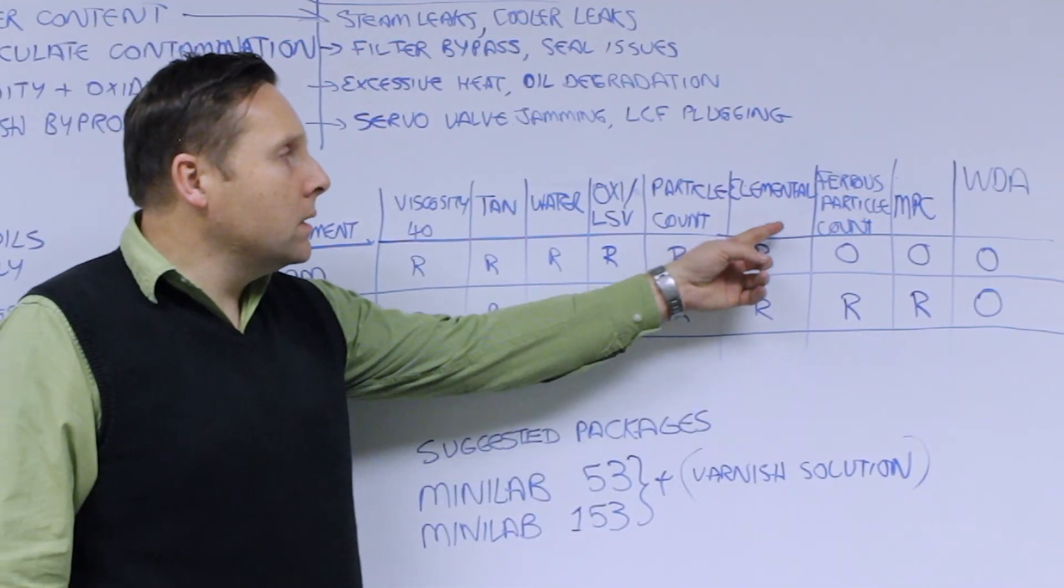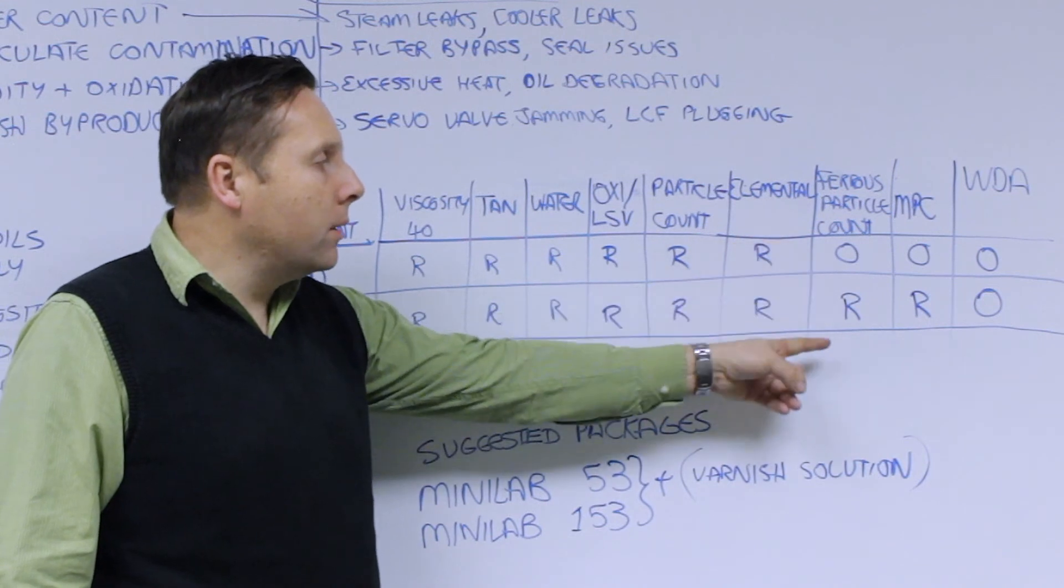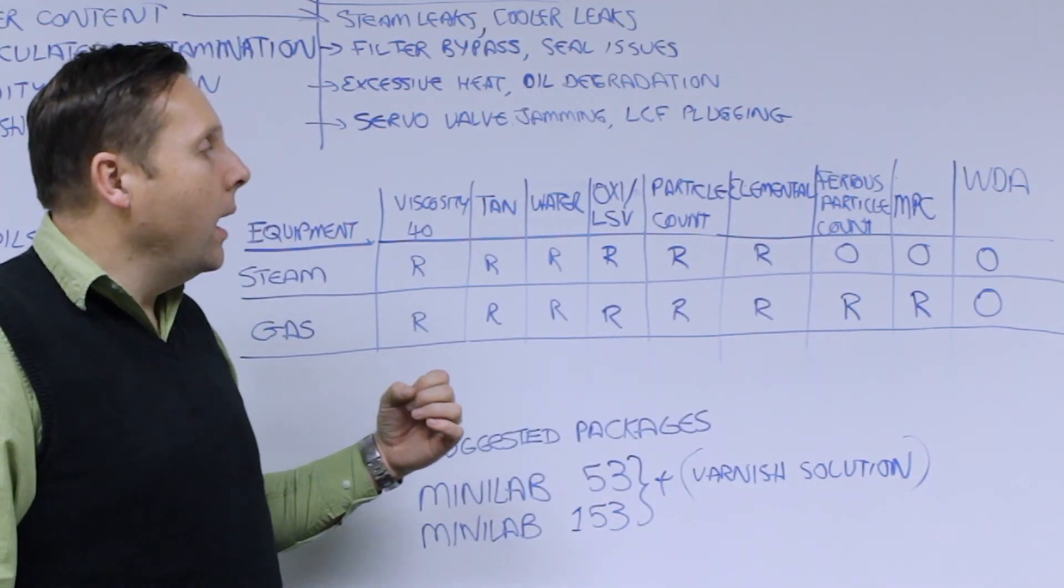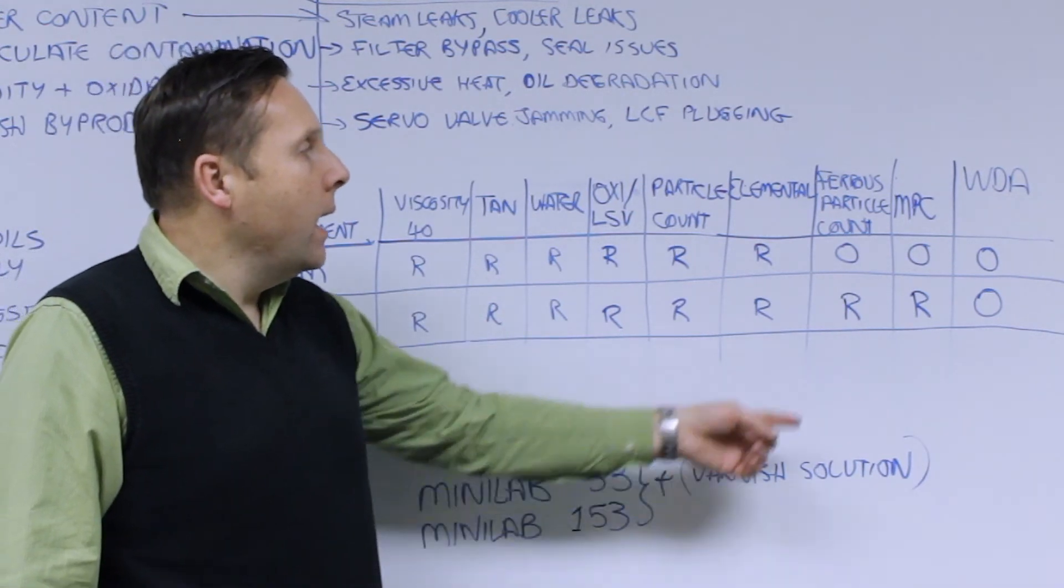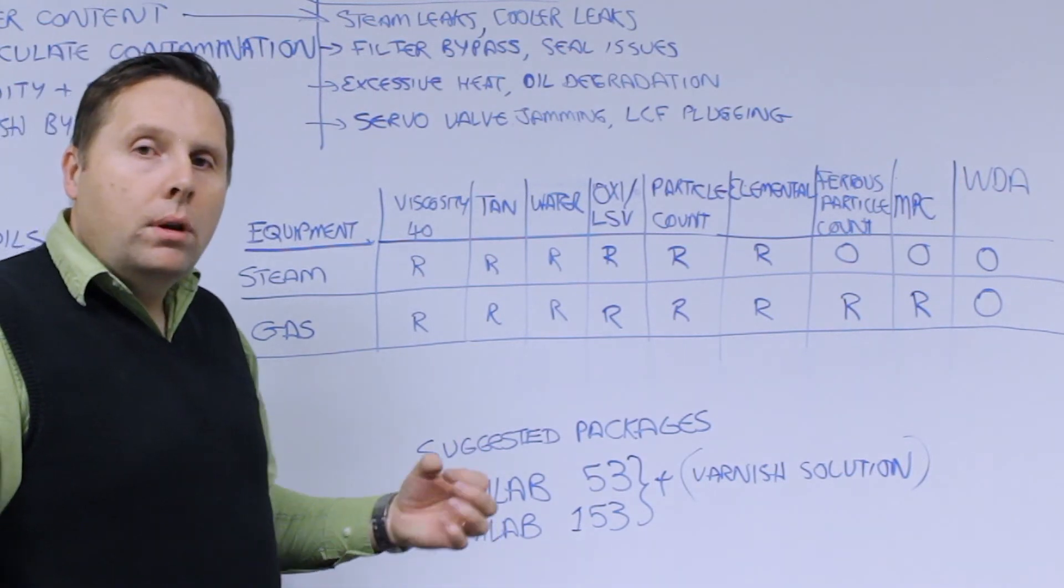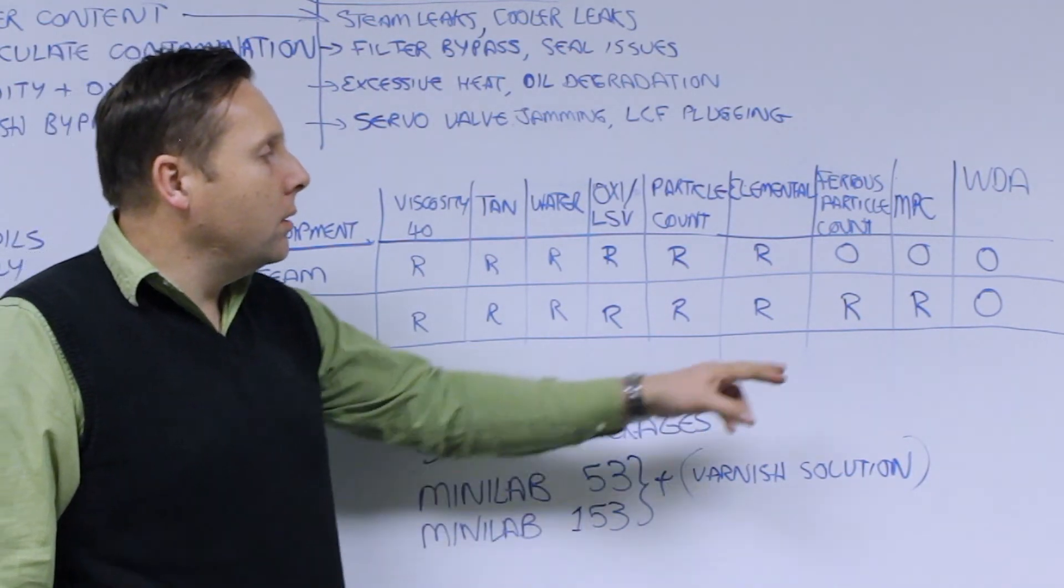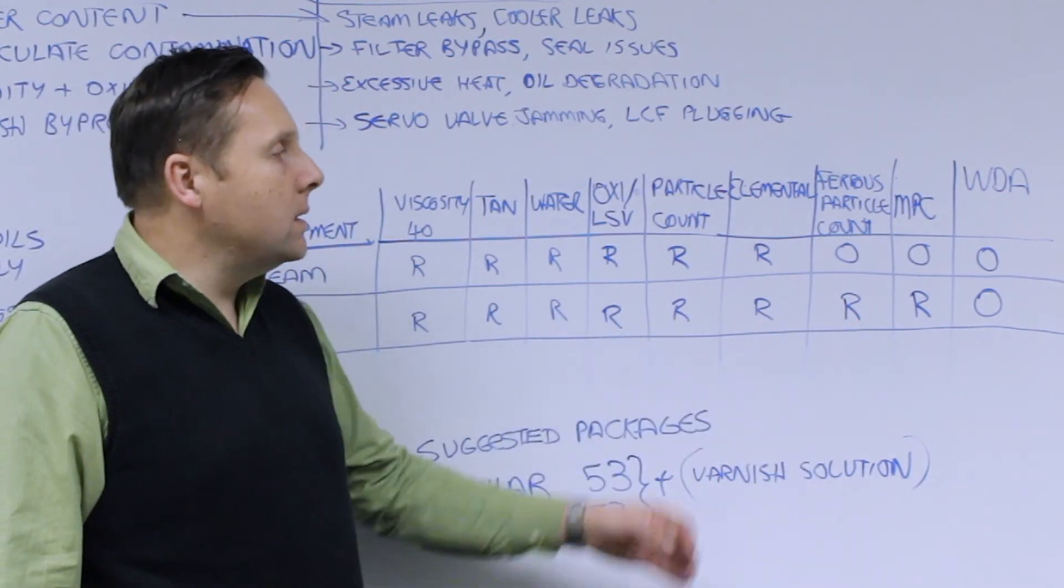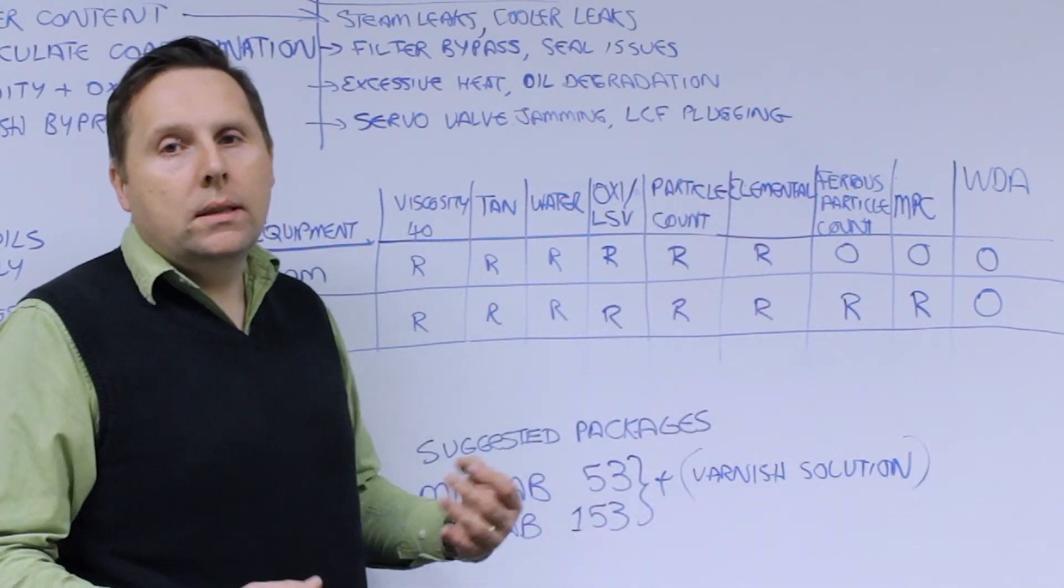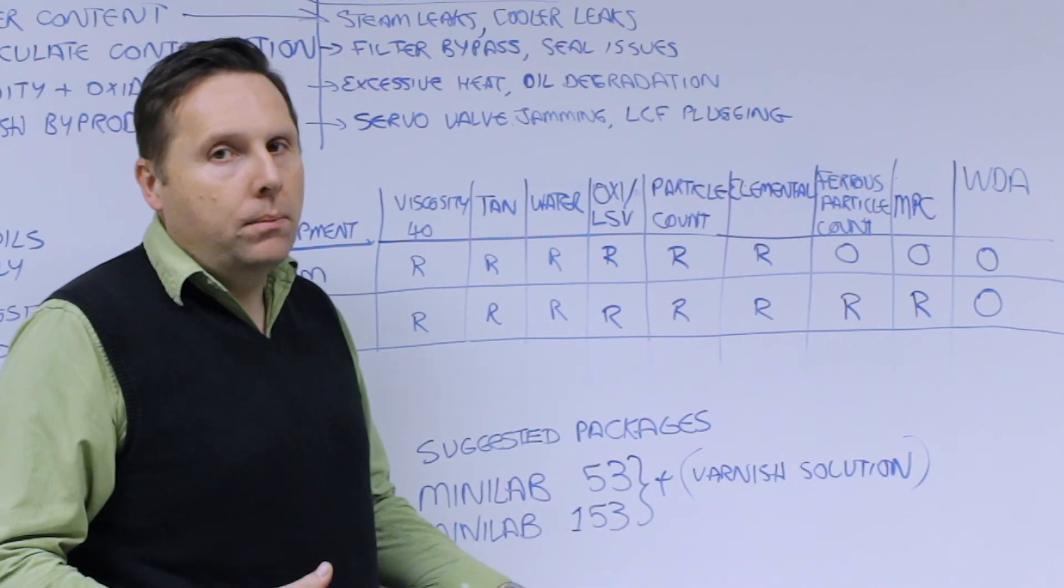We want to look at ferrous contamination, ferrous particle count on gas turbines, particularly of turning gear systems and not so much critical on steam turbines. We want to look at the membrane patch colorimetry which is the varnish tester. That's definitely recommended for gas turbine systems. It's optional for steam turbines and of course wear debris analysis is optional anytime you indicate a potential problem.